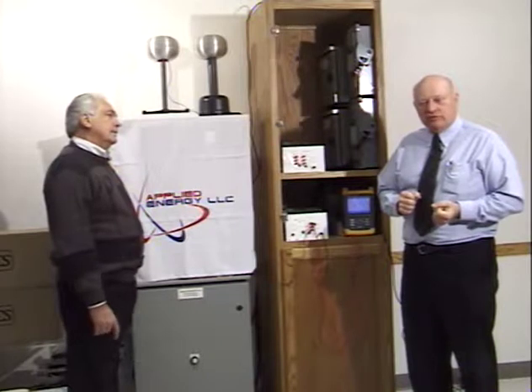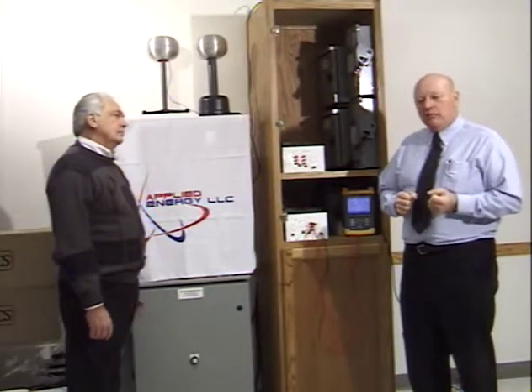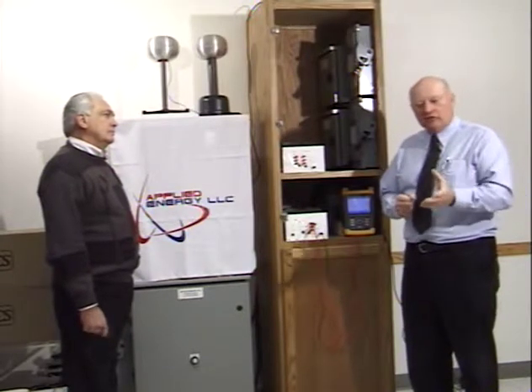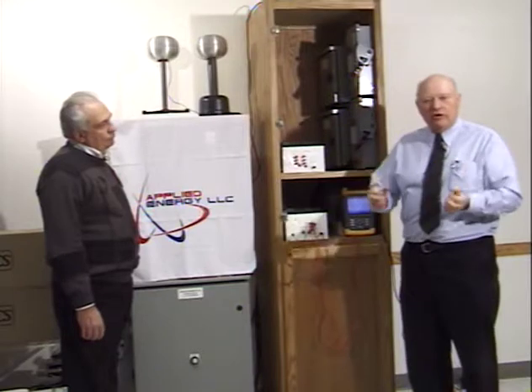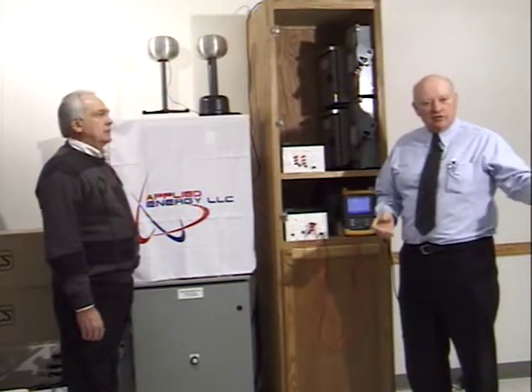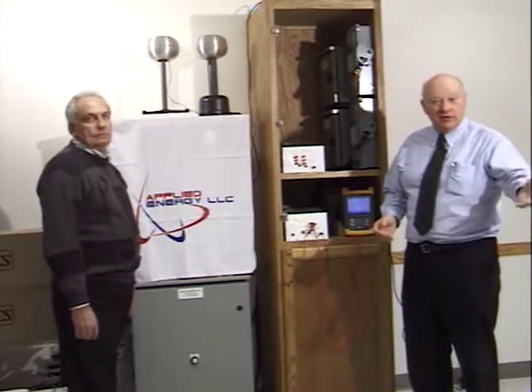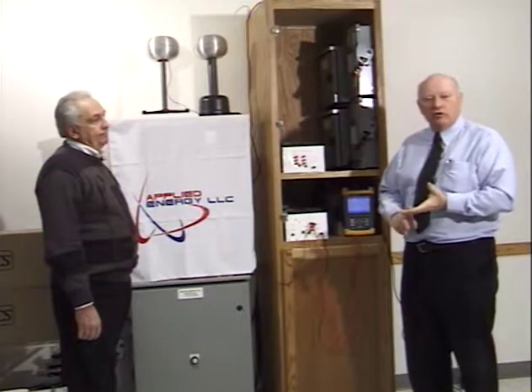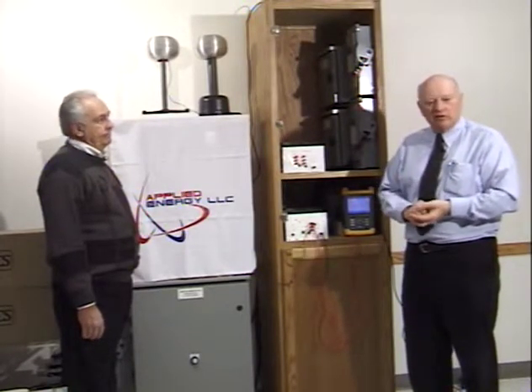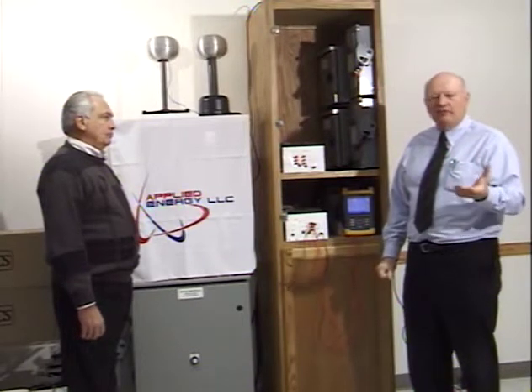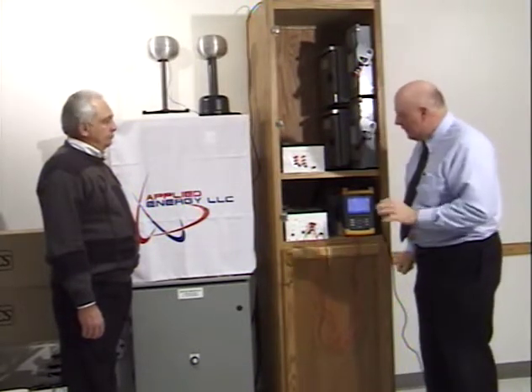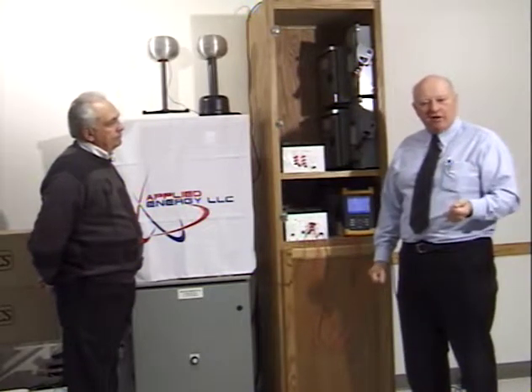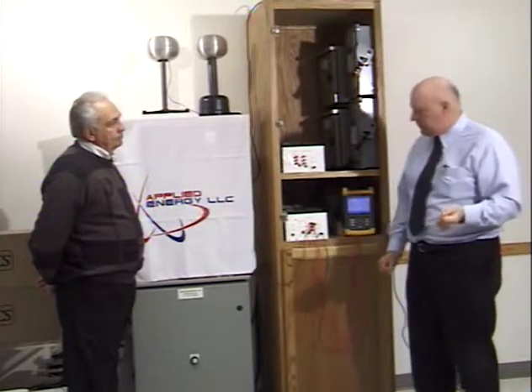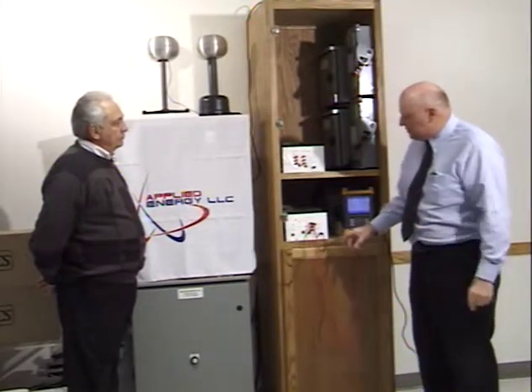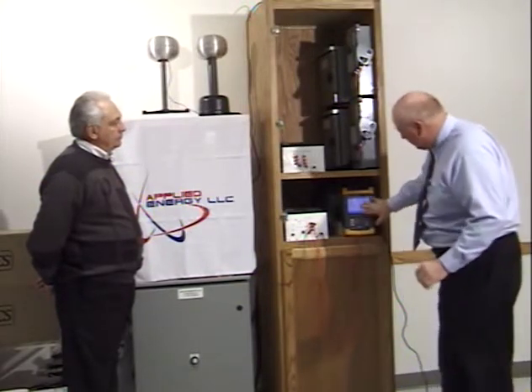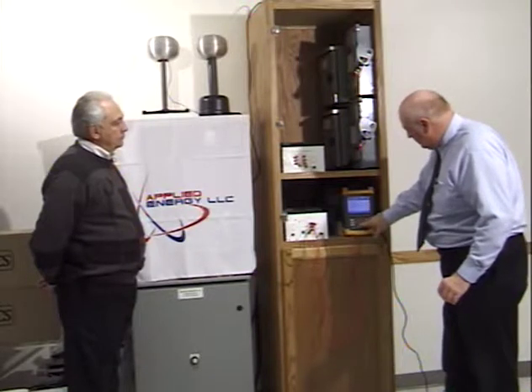In many distribution systems where you have sensitive equipment, you have a problem with electrical pollution or noise from all over the place. Mother Nature makes noise every time there's a storm. Your neighbors make noise, comes in on the power distribution system. All of your adjustable frequency drives, switch mode power supplies, which is power supplies in every computer, every CNC control, and many other pieces of equipment. As loads are turned on and off, you'll have spikes in voltage and surges in current that will affect this. One other aspect is harmonic distortion. I'm going to switch from our live scope mode to harmonics.